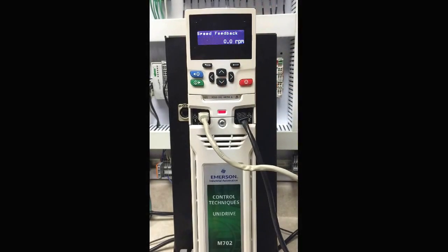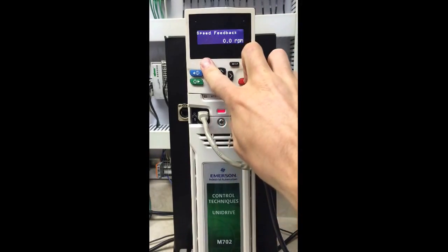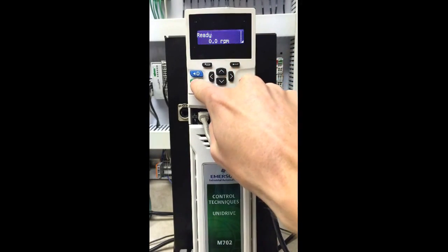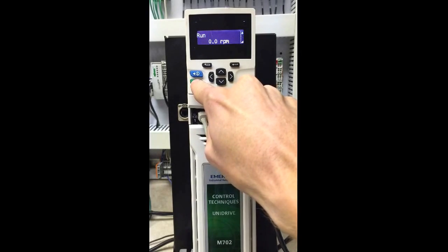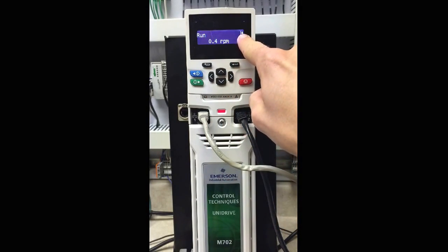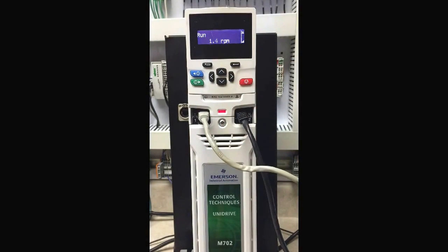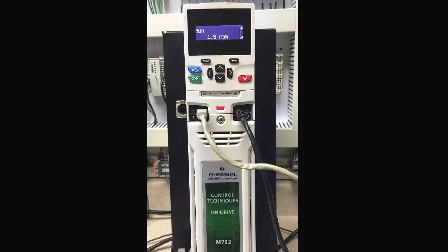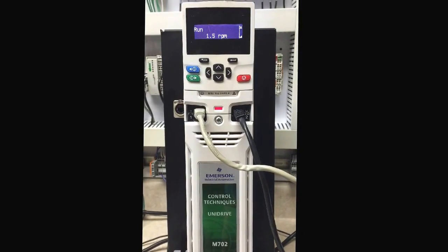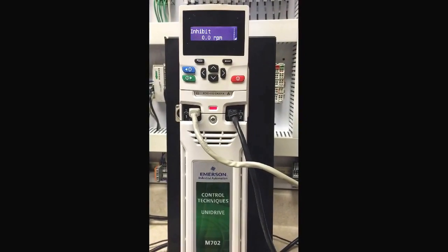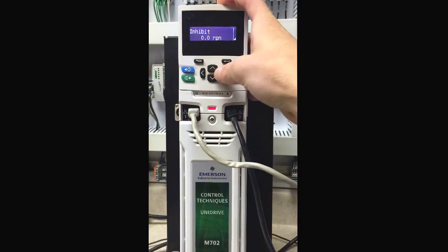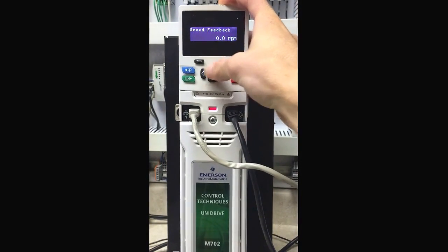We'll come up here, we will enable the drive. We can see our ready. And we'll give it the run command. And now we have our little bell, and we'll also see the word auto tune as the drive performs the auto tune. Once the auto-tune is complete, we will disable the drive and save our parameters.